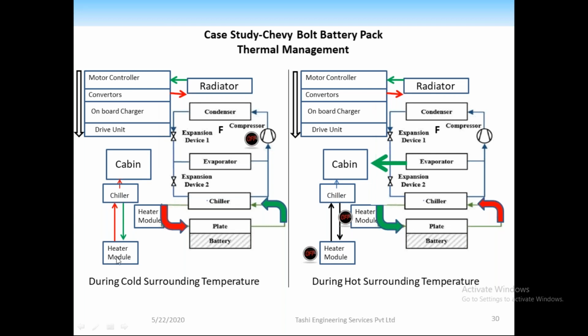For cabin heating in cold climate, I turn the heater on so that the fan blows air into the heater, and that hot air is let into the battery pack, keeping the battery pack temperature warm. In this kind of system our compressor is not working. But importantly, the motor, controller, and converter cooling doesn't change whether we are in a hot or cold climate - these will always generate heat that needs to be removed, so these two arrows remain the same irrespective of the climate we are in.